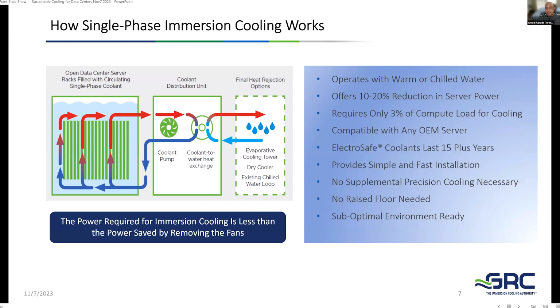Now to reject this heat, we transfer it to a water loop using a plate heat exchanger. And so, depending on the solution, the outdoor climate, the region, and the density that you are working on, we can use a chiller at a high temperature, or cooling towers, or dry coolers, or adiabatic dry coolers to reject the heat into the environment. So this is how the solution simply works. What is the benefit of it? The benefit is a sustainable solution which helps the customer take care of higher density IT equipment and more power consuming CPUs, but operating with an efficiency which is much higher than what traditional air cooling can provide.